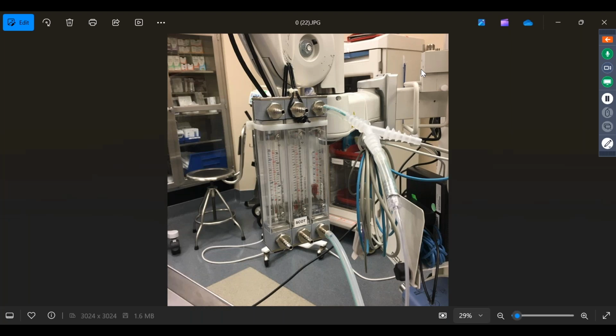When I'm checking the flows, I'm connected up. I'm either using the gas analyzer in the machine, or I'm using my GE SAM module to make sure I get a 25-75 mix. And then I'll go to 1 liter of N2O, 1 liter of oxygen, and I'll want to see a 50-50 mix. Then I'll do a 50-50 of air and O2, and I want to see a 60% mix on there.